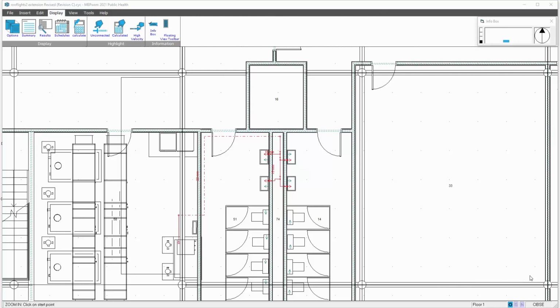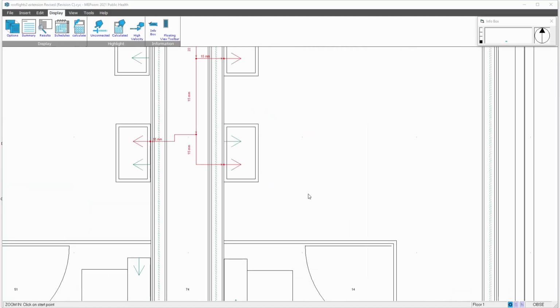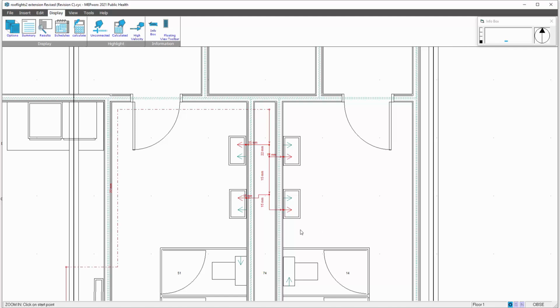This video continues with the addition of circulating returns so we can simulate our circulating draw-offs. In the previous video, we ran in our pipe runs for the hot water. What we need to do now is put what we call a circulating tap-off point in. This is the point at which we're tapping off to keep our dead legs to a minimum. Ordinarily, we'd probably position it at the end of this pipe run here.